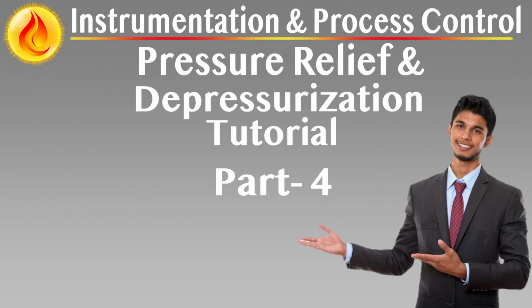Install meters in elevated, accessible, and well-drained locations, especially when condensable vapors or liquid carryover are expected. Use redundant or bypass arrangements only when necessary, as flare lines should remain as simple and direct as possible.